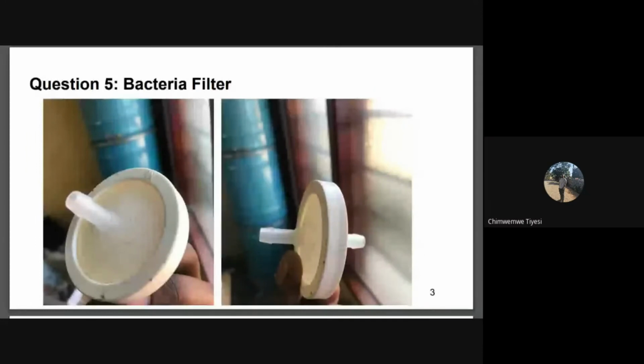Microfiltration membranes can have either an isotropic or asymmetric pore structure. Asymmetric membranes are used with the skin side facing the feed, that's the inlet, to minimize surface fouling. Surface fouling can be easily defined as the accumulation of unwanted materials on solid surfaces. So the in and out might mean that the type of bacterial filter you used has an asymmetric membrane to prevent surface fouling. So remember to place them in the direction of flow as indicated on the side of the bacteria filter. Thank you, Maui.